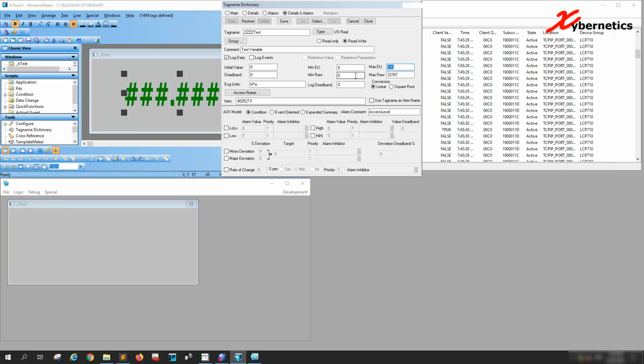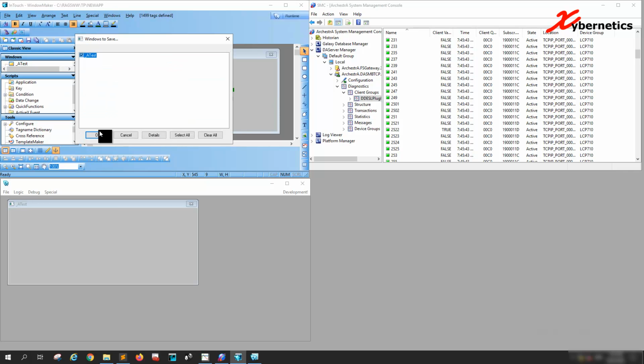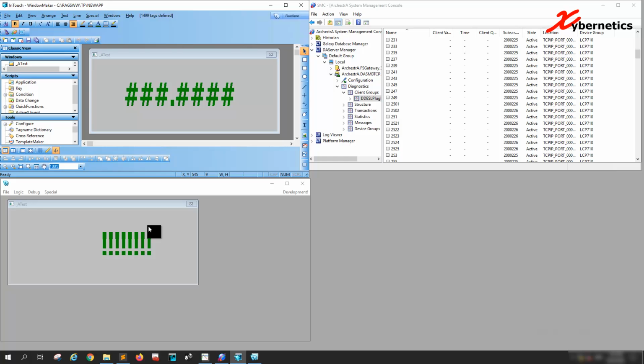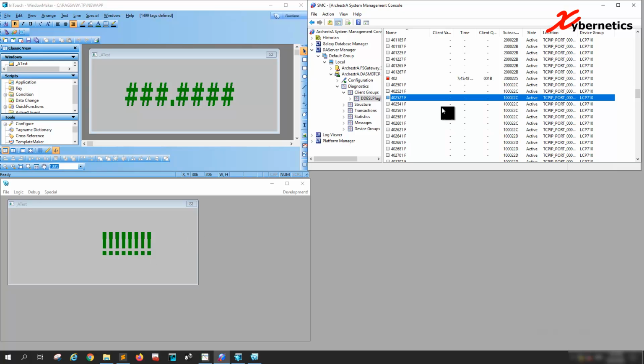So it's right now 0 to 100, 0 to 32,767. So you save it, close, hit OK, and then you save it again. File, save. Once you save it, this gets updated. And if you scroll down here to 40,027 here, this guy here, it's not being read yet. That's why I'm showing exclamation yet. So as soon as this thing refreshes, this will show you a value here. And you'll realize that the values here matches the Modicon.